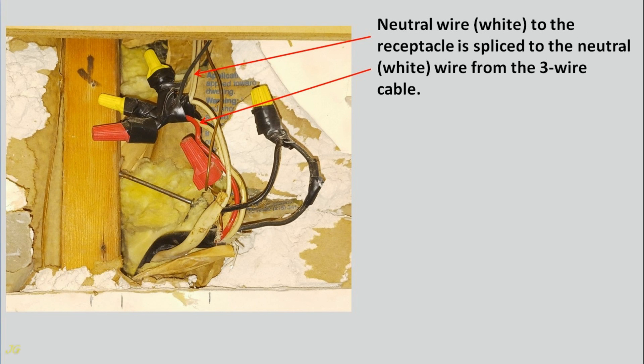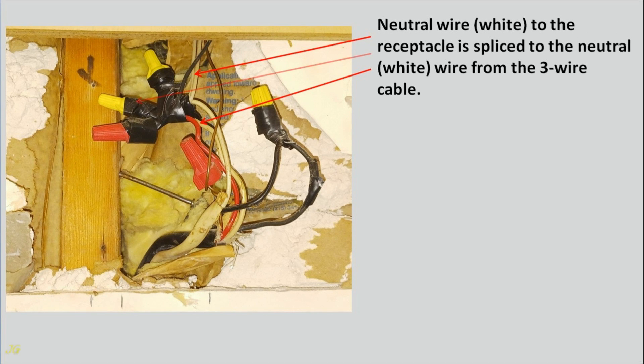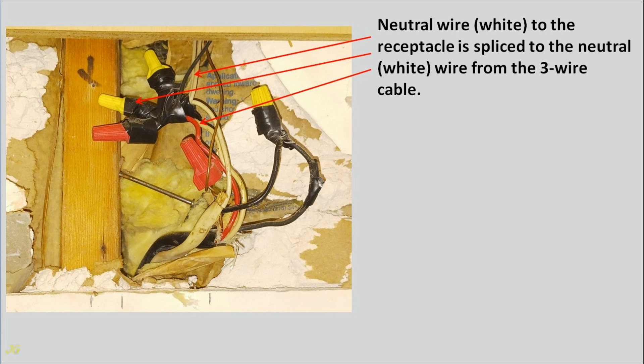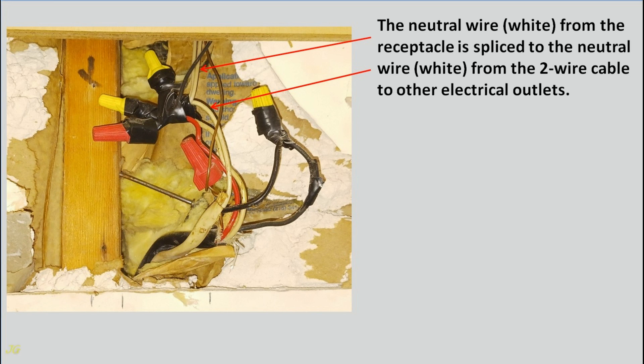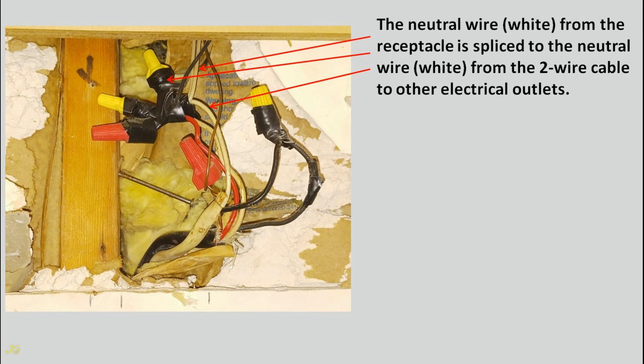Neutral wire white to the receptacle is spliced to the neutral white wire from the three-wire cable. The neutral wire white from the three-wire cable is spliced to the neutral wire white from the two-wire cable to other electrical outlets.